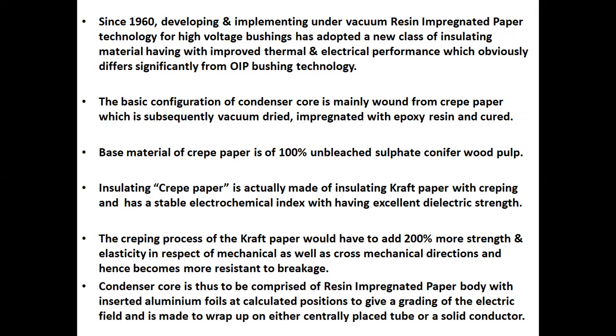The base material of crepe paper is 100% unbleached sulfate conifer wood pulp. Insulating crepe paper is actually made of insulating kraft paper with creping and has a stable electrochemical index with excellent dielectric strength. The creping process of the kraft paper adds 200% more strength and elasticity in the mechanical as well as cross mechanical directions, and hence it becomes more resistant to breakage.